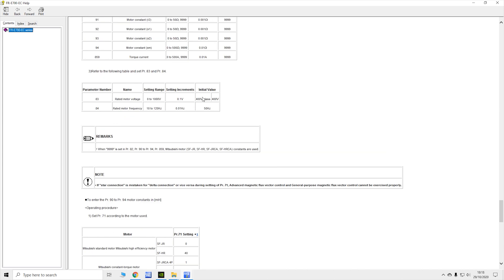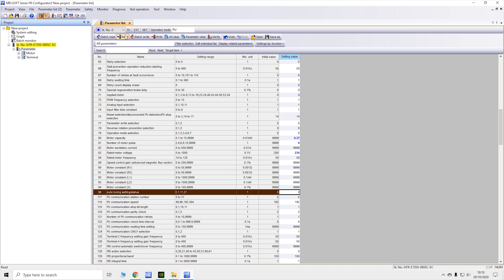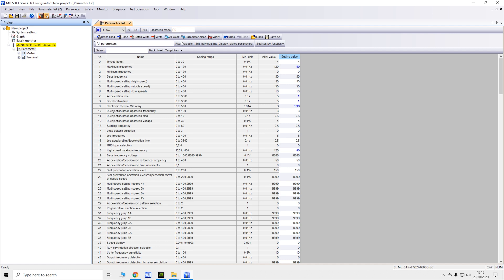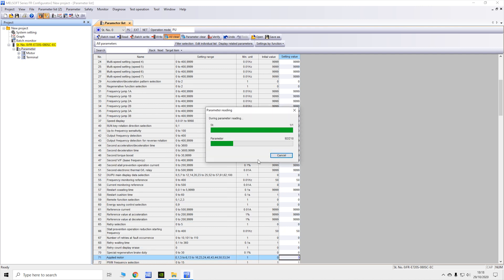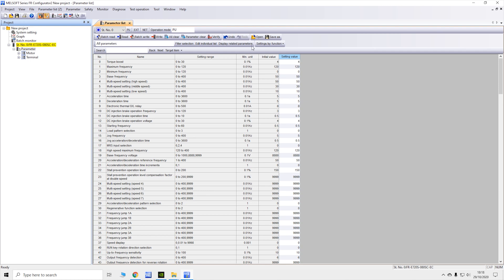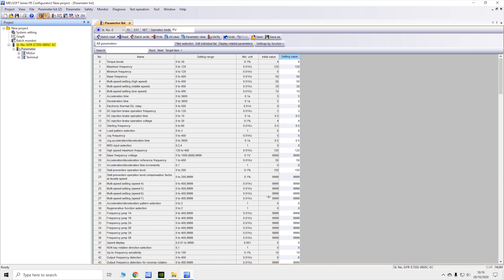I definitely encourage you to use FR Configurator — it is so much easier to set up your drive. If you press Read it reads one selected parameter; Batch Read reads all of them. The same applies for Write. You can also do a Parameter Clear or All Clear. We're going to wipe the drive completely. This shows you how to extract the parameters from the drive. After Batch Read, we'll wipe the whole thing. There we go — all setting values have returned to default. This is what you see on a brand new drive.